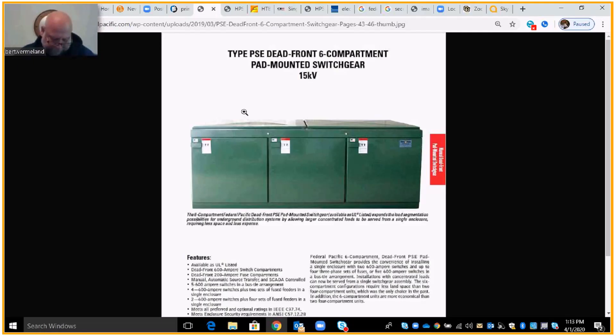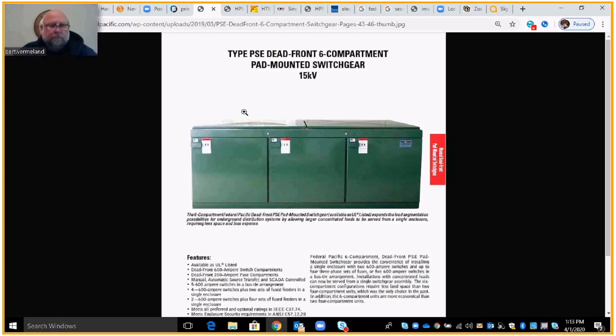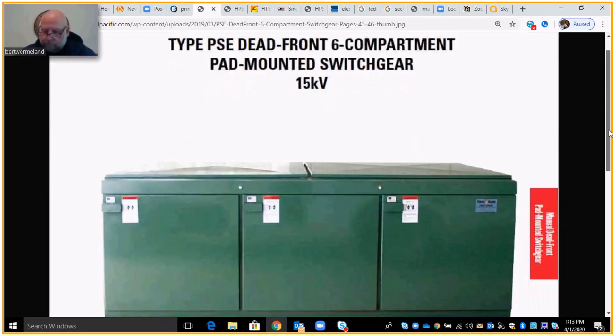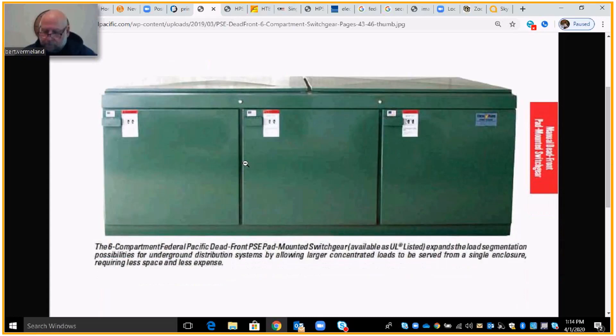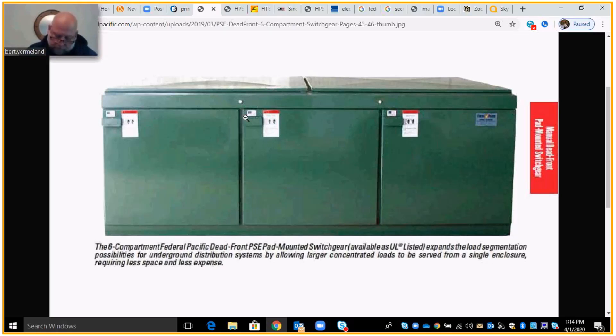Next is what they call dead front switchgear or pad-mounted switchgear. We discussed previously how the book says switchgear are all switches, but that really isn't true — this is an actual switchgear. After the dip pole, you can have either a feeder or a tap coming down. A feeder will come into what they call a switchgear, which has compartments. You can have a four-compartment or six-compartment switchgear — those are the most typical. The compartments are designated by numbers. In this example I have here, this is a six-compartment switchgear.